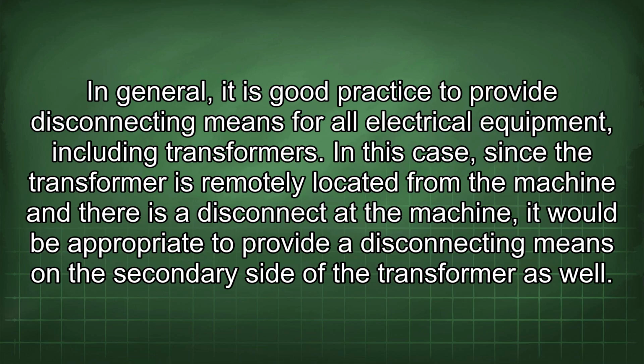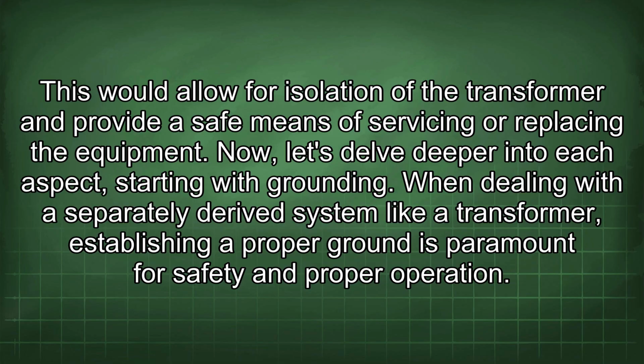In general, it is good practice to provide disconnecting means for all electrical equipment, including transformers. In this case, since the transformer is remotely located from the machine and there is a disconnect at the machine, it would be appropriate to provide a disconnecting means on the secondary side of the transformer as well. This would allow for isolation of the transformer and provide a safe means of servicing or replacing the equipment.